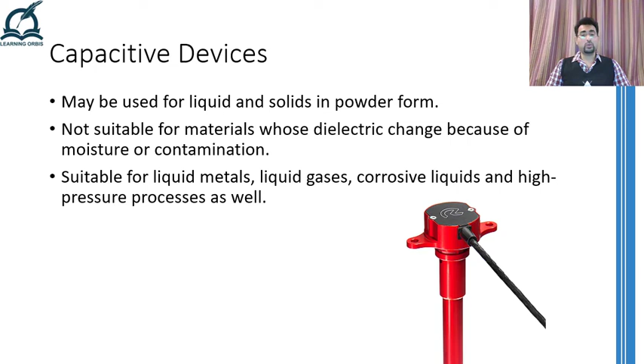If the involved liquid has negligible conductivity, then two bare metal plates or concentric pipes can be inserted into the liquid to perform the level sensing. However, if the involved liquid is conductive, then these plates can be coated with suitable insulators. The height of the liquid between the two metal plates will dictate the overall dielectric of this capacitor and hence the overall capacitance. By monitoring the change in capacitance, we can easily figure out the level of the liquid between the plates.